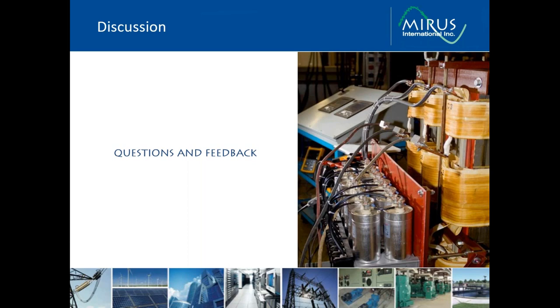So it'll give you voltage and current, power, kilowatts, kVA, kVAR, and harmonics, up to the 63rd harmonic, current harmonics and voltage harmonics. So that is an option. If somebody chooses it, it is standard on our larger filters and our really large filters, optional on the smaller ones. The next question is about power factor correction.